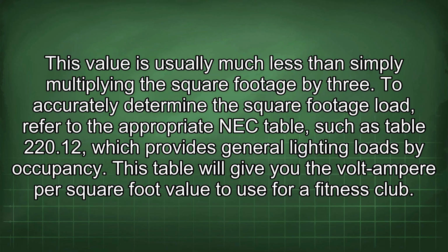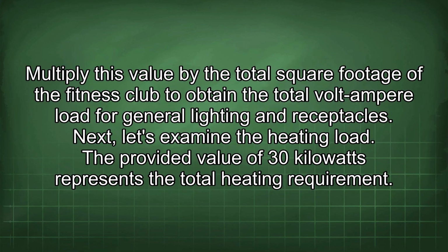To accurately determine the square footage load, refer to the appropriate NEC table, such as Table 220.12, which provides general lighting loads by occupancy. This table will give you the volt-ampere per square foot value to use for a fitness club. Multiply this value by the total square footage of the fitness club to obtain the total volt-ampere load for general lighting and receptacles. Next, let's examine the heating load.